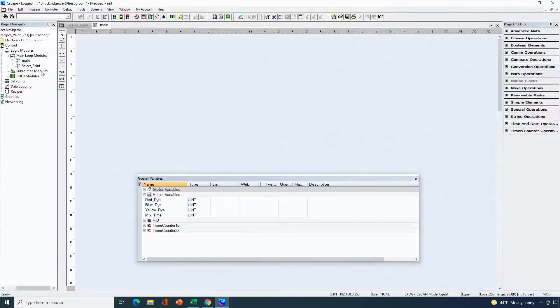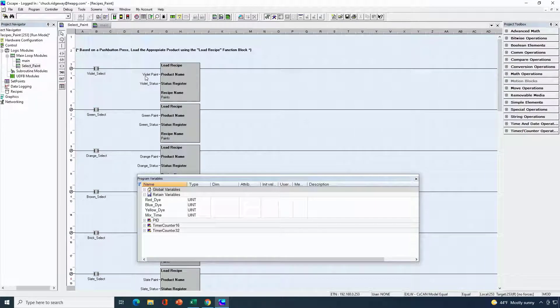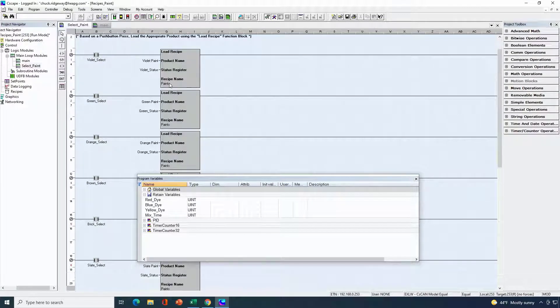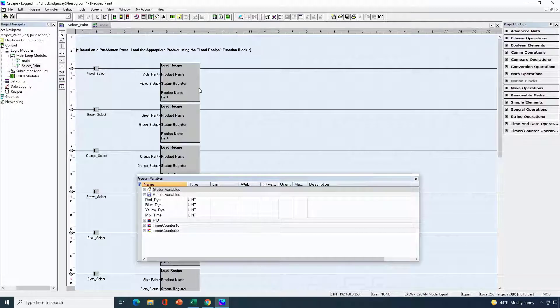Let me exit the graphics editor and go to my select paint logic routine. Here's the one for violet — this is the bit that turns on when I press that push button to load violet. When that contact is on, the load recipe function block executes and loads the product violet paint. It also has a status register tied to it — if there's a problem, such as a missing or pulled microSD card, the status register will indicate that. For each of the different products, I've got a different load recipe function block configured to load that particular product's parameters.